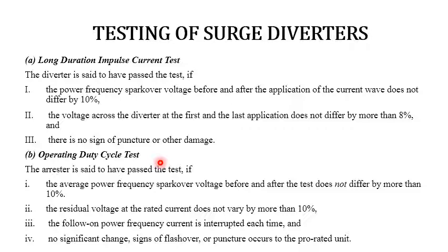The arrester is said to have passed the test if the average power frequency spark-over voltage before and after the test does not differ by more than 10%, and the residual voltage at the rated current does not vary by more than 10%. The follow-on power frequency current is interrupted each time, and there is no significant change or sign of flashover or puncture in the rated unit. Then we say that it has passed the test.